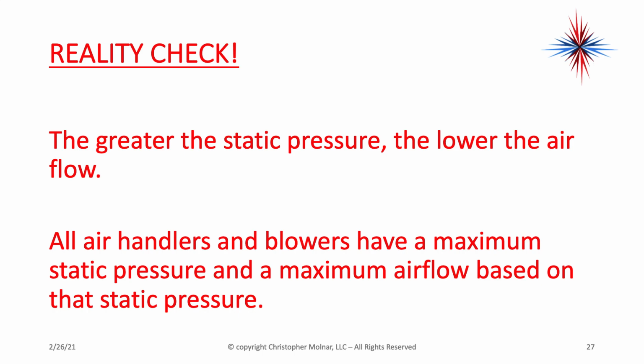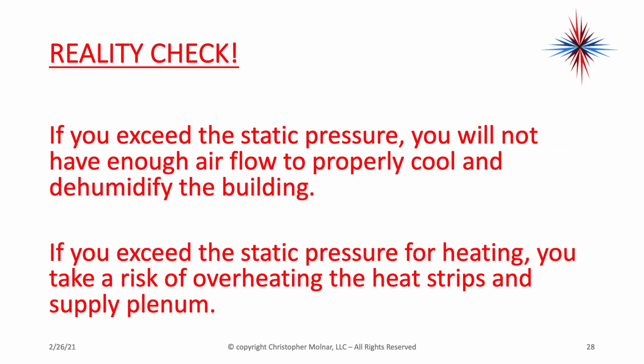Reality check. The greater the static pressure, the lower the airflow. All air handlers and blowers have a maximum static pressure and a maximum airflow based on that static pressure. If you exceed the static pressure, you will not have enough airflow to properly cool and dehumidify the building. If you exceed the static pressure for heating, you take a risk of overheating the heat strips and the supply plenum.